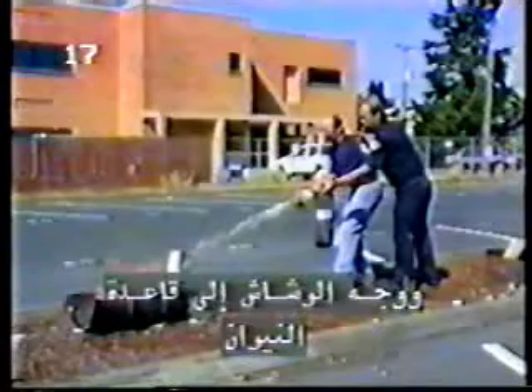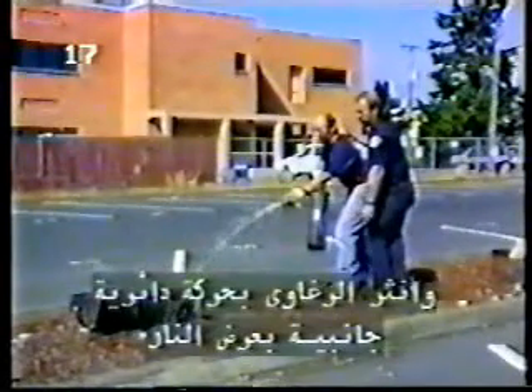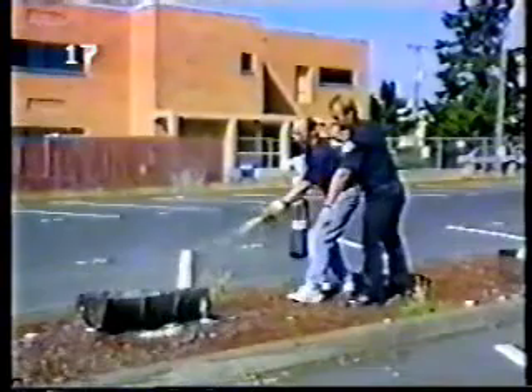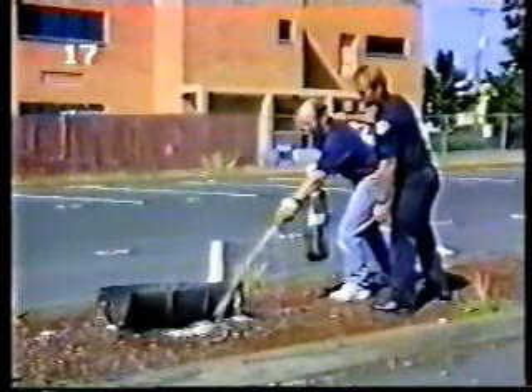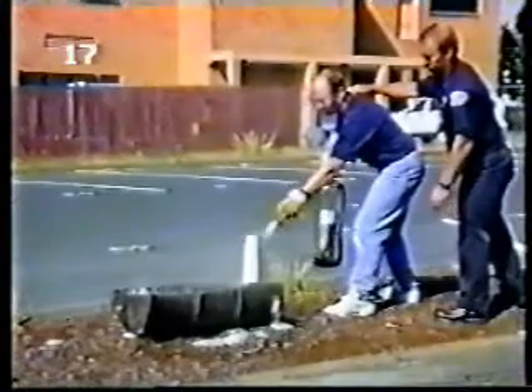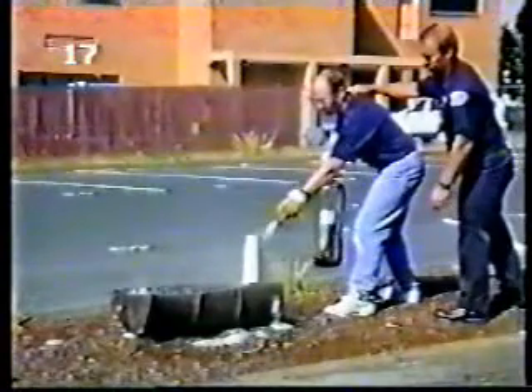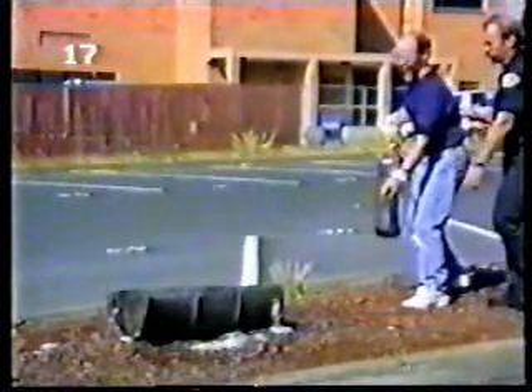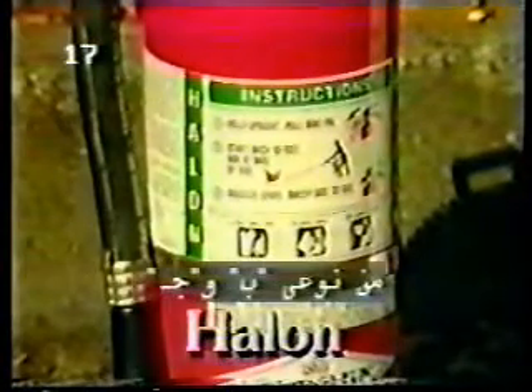To operate a Halon 1211 extinguisher, carry it by the top handle to the fire location. You will have to get quite close to the fire because this extinguisher has a very limited range. Aim the discharge at the base of the flames, sweeping the flame from the burning surface. Keep applying the agent even after the flames are extinguished to prevent reignition.